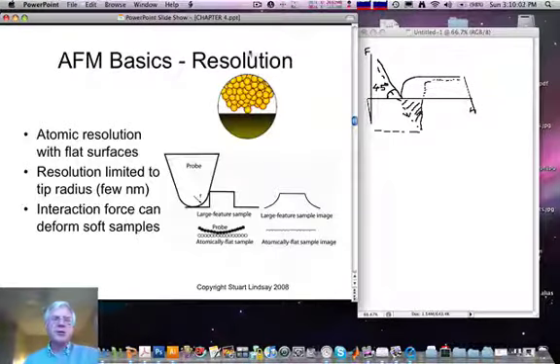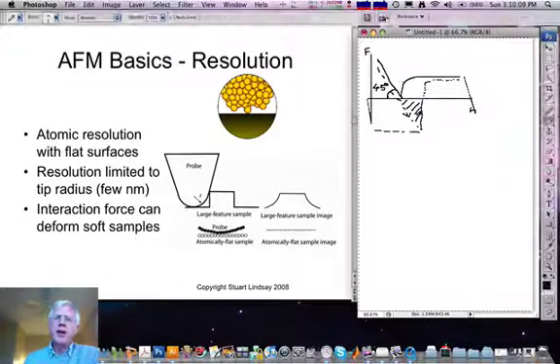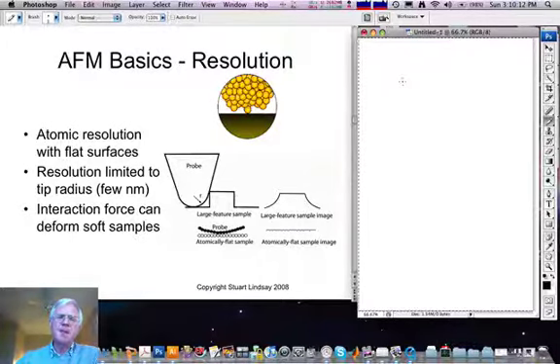Finally, we turn to the question of resolution in an AFM. AFMs can get atomic resolution, but only on very flat surfaces, as illustrated in this figure right here. As soon as the surface ceases to be flat, atoms on the end of the probe can no longer dominate the imaging, and then what one samples is the long range geometry of the probe.